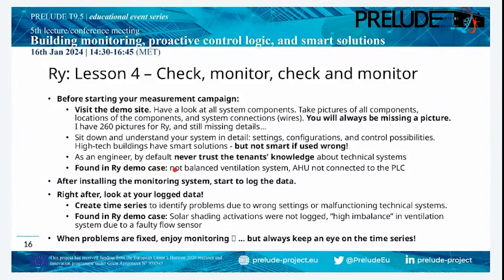For instance, in RY we found an unbalanced ventilation system, and we found that the air handling units were not connected to the PLC. It was just running on step 2 all the time, whereas the PLC can go to step 1, 2, and 3 when necessary.